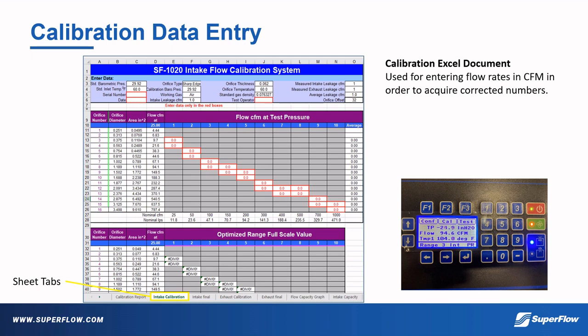Right now, intake calibration is selected, followed by intake final, exhaust calibration, and exhaust final. The tabs labeled intake final and exhaust final are used to record the leakage of the particular bench. We will discuss what this means later. After the flow rates are recorded in the calibration tabs, correcting numbers are generated in the calibration report tab. These numbers are entered into the flowcom to calibrate the bench.